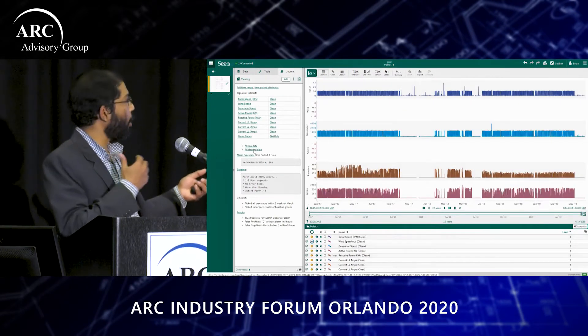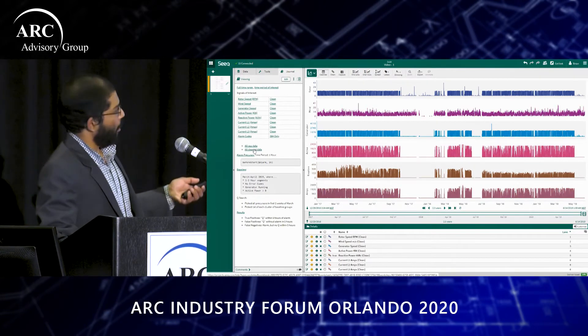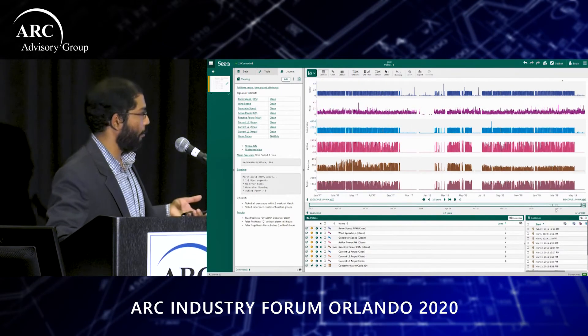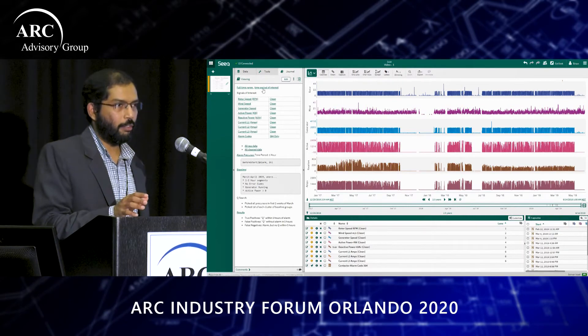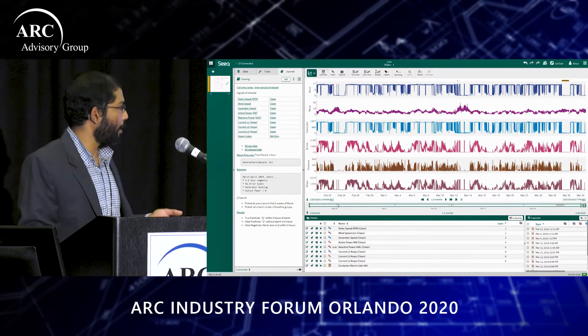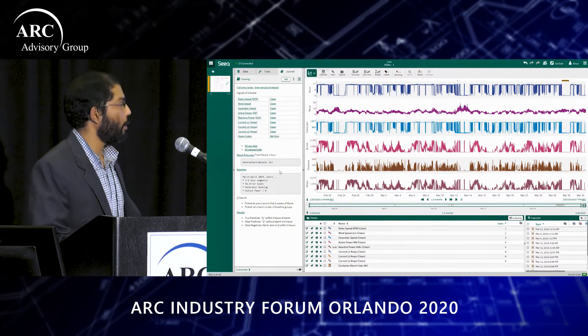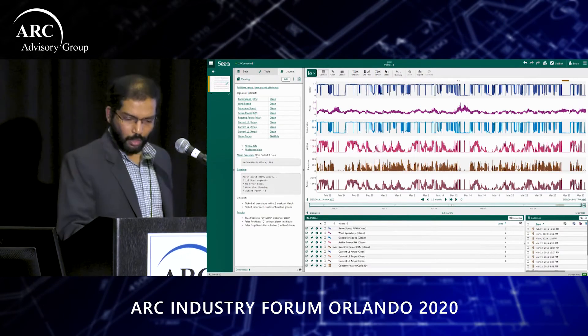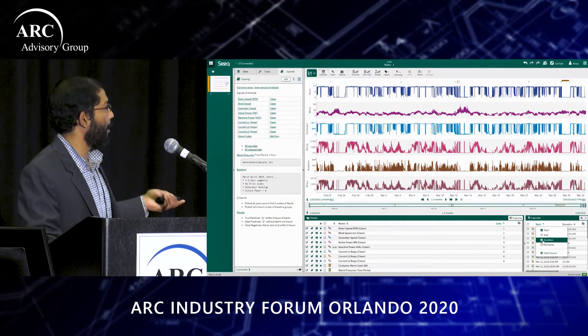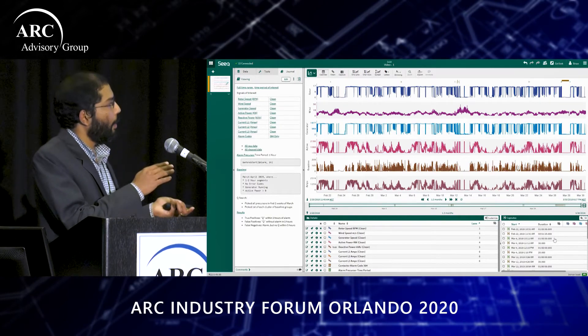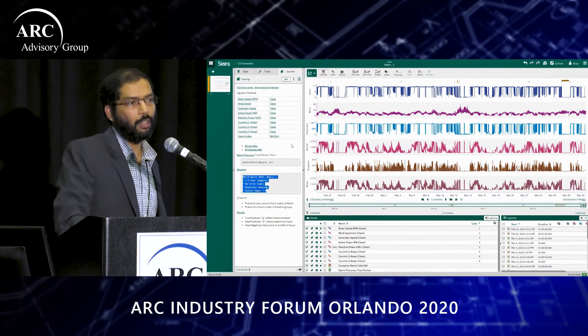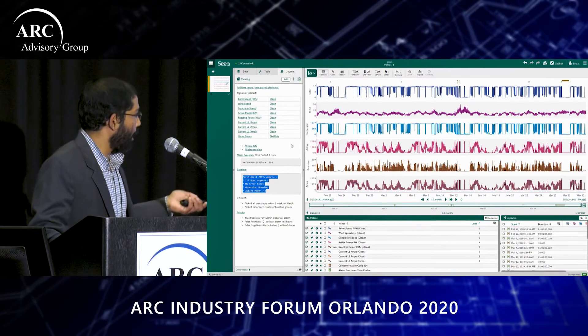We got our raw signals, cleaned them up, and defined what problem we are looking to identify — alarm code 364. This entire dataset was for a two-and-a-half-year period from one particular wind turbine. The issues mostly occurred within a two-to-three-month timeframe, specifically February to April of early 2019. We settled on a one-hour alarm precursor time period, and we told the model what to look for as target behavior. We also told it what baseline behavior looks like: one-to-two-hour time segments in the same general time period when there were no error codes, the generator was running, and active power was zero.